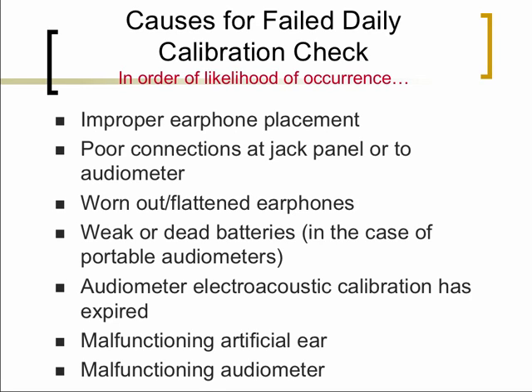There are a number of simple reasons why you might have failed your daily calibration. Some of the things you can troubleshoot, or if you have a reserve replacement you can replace, and then you might find that you're back in calibration. In the hierarchy of likelihood, it could include improper earphone placement, poor connections at the jack panel, which might have rusted or become loose, or worn out earphones. If you're using a portable audiometer, it could be just dead batteries. It could be that the audiometer's electroacoustical calibration has expired. And one of the things that the engineer or whoever is doing this annual calibration would do is typically put a sticker at the back of the audiometer with the date on which the calibration was done or when it is due.